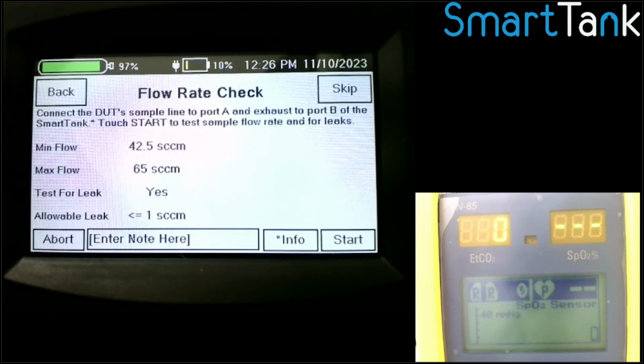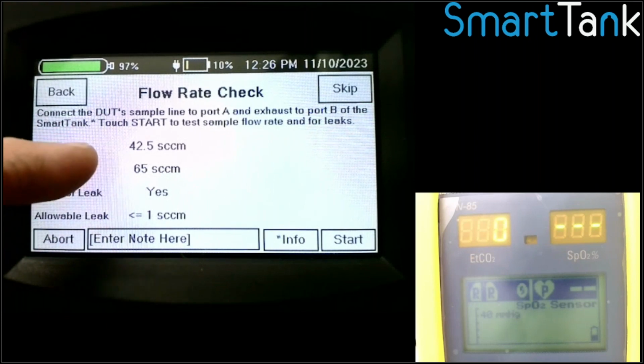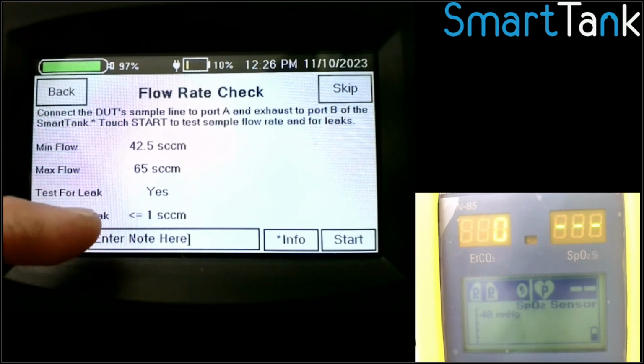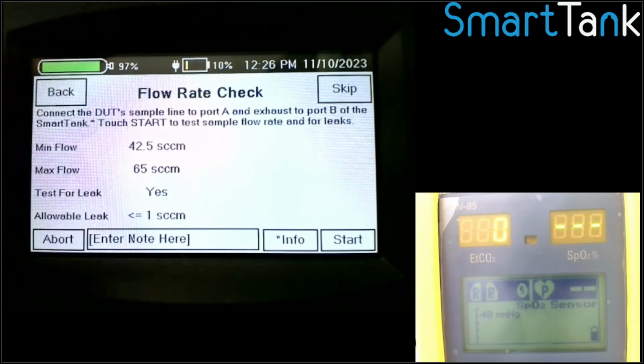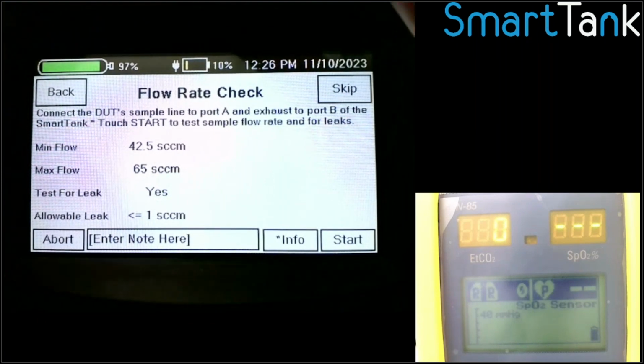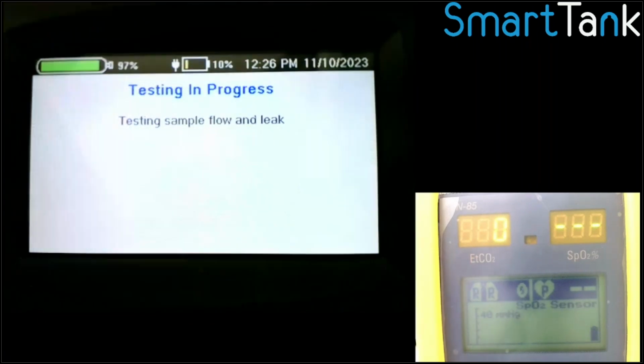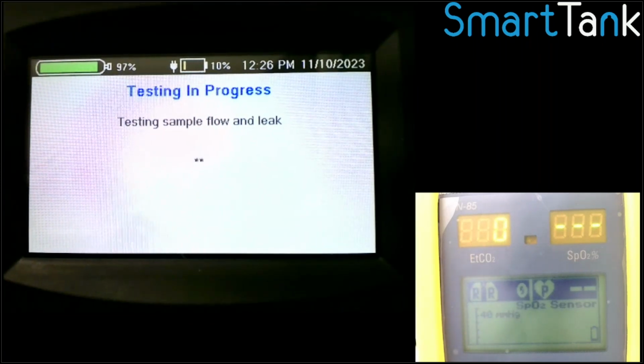So now we're on the second of 3 tests within the sequence. All it's going to do is check for our flow rate, which needs to be between those values. And it's going to actually do a leak check because we have it hooked up to this exhaust port. So I'm going to hit start. And it will take about 12 seconds to do this. It's testing both for leak and sample. And notice that I haven't touched any of the cords or the tubes or connections. I don't have to get out a flow meter. I don't have to get any of that stuff pulled together because it's all built into the SmartTank.